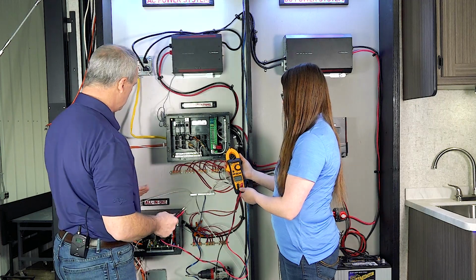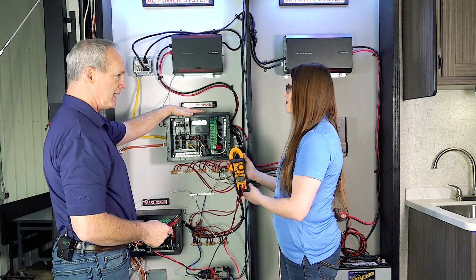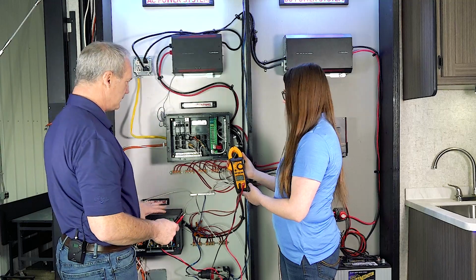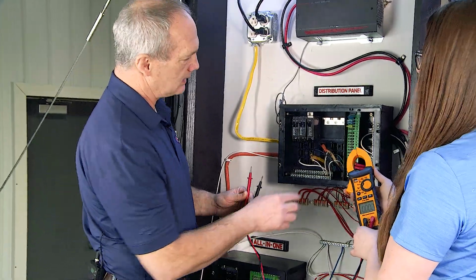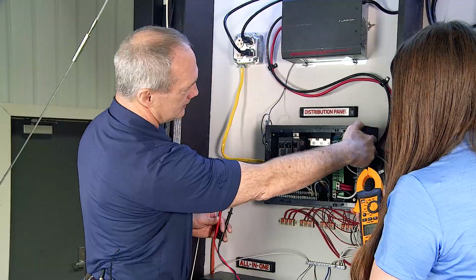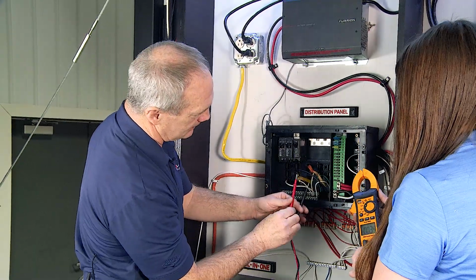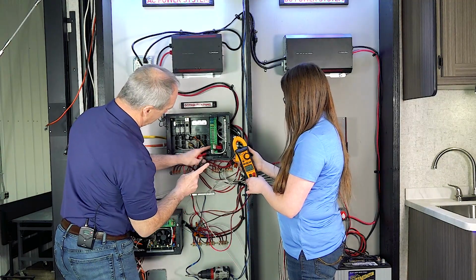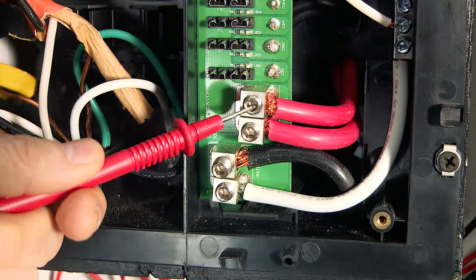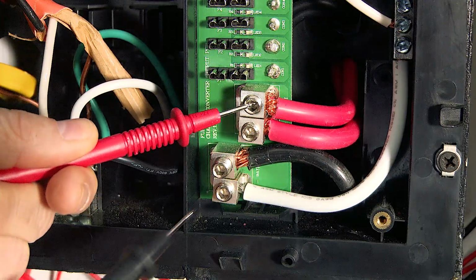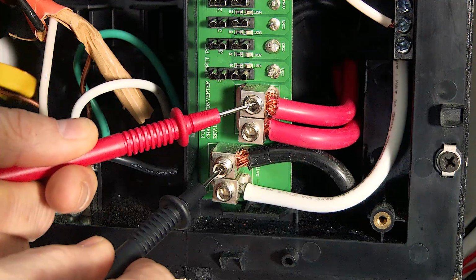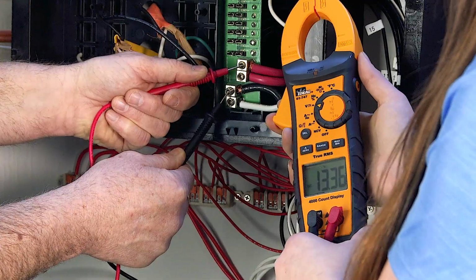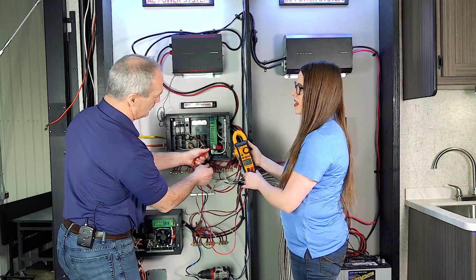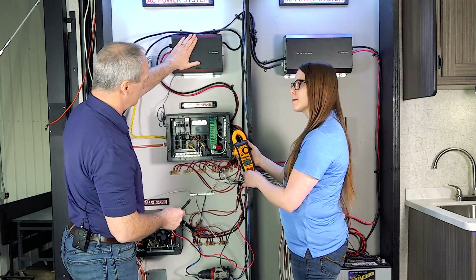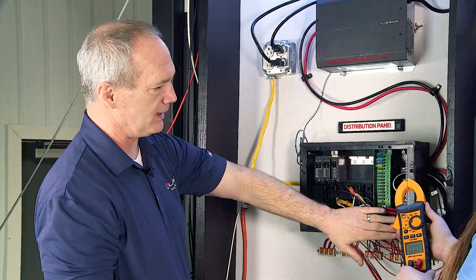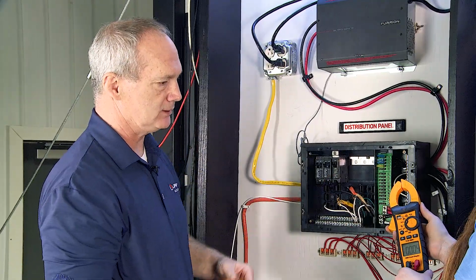So we're good, we know it's receiving that power, and we're eliminating it as we go, just like before. Now we're looking at these two wires going into the distribution panel: the power lead coming in here and the negative lead here, and we should have roughly 13.5 volts coming out of the converter, and we do. So we now know the converter is supplying the distribution panel with the proper voltage to charge that battery.